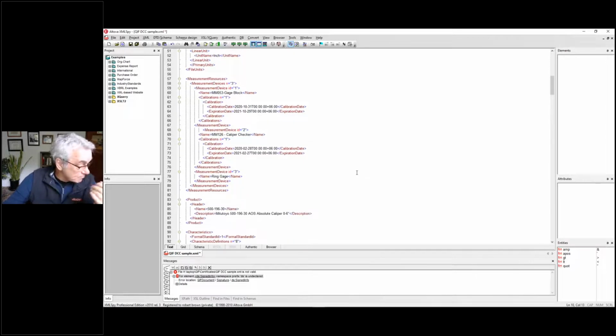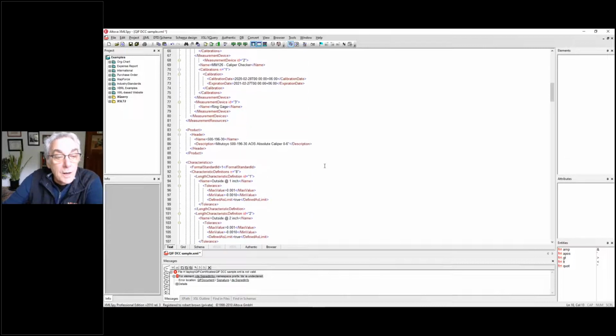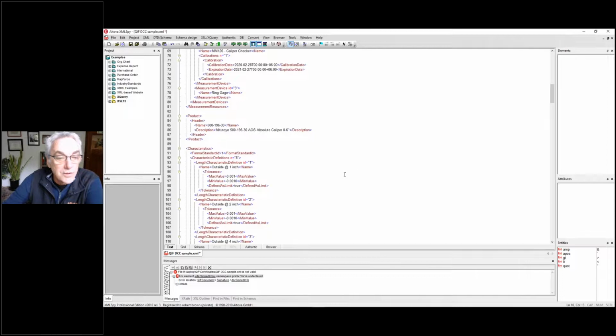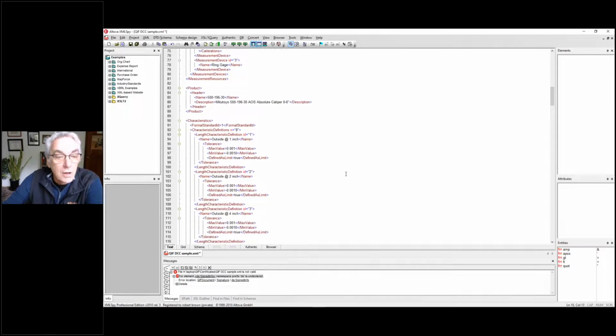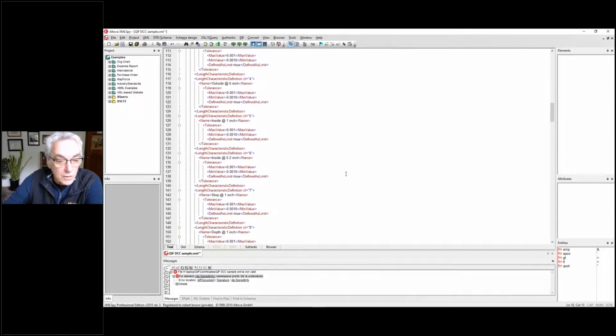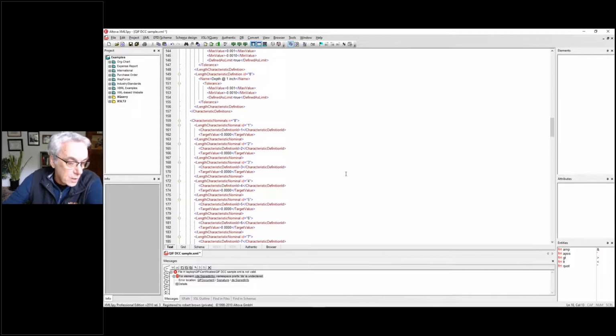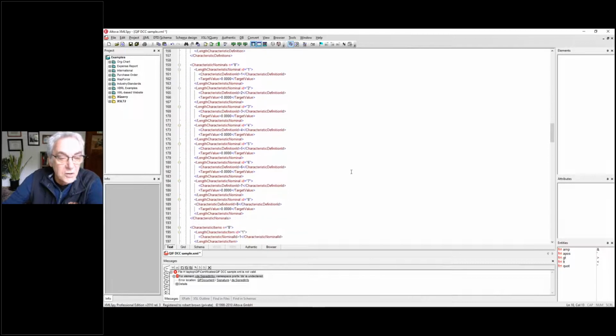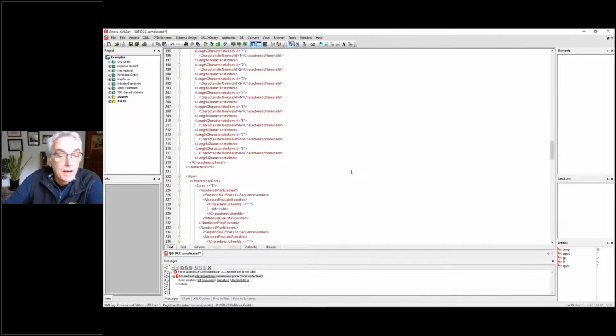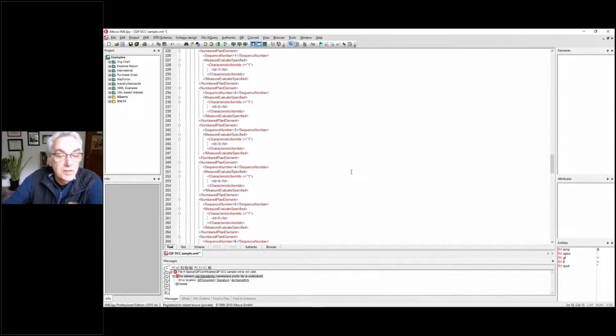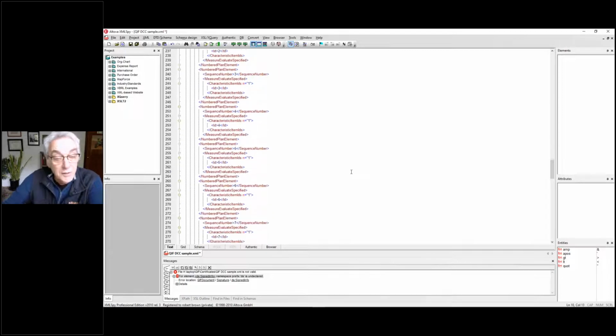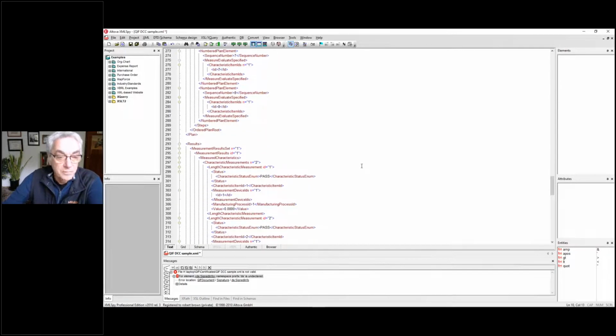The product, again, that caliper is a 500-196-30, which is a product code, and the description is again a 0 to 6 inch caliper. Characteristics, again, as we have the test points, we would understand it outside at 1 inch with its tolerance information. I'll just go down the line as we scroll to all of the different test points. We certainly have a nominal, and if we're doing an offset, so everything is 0. Ideally, we have the plan, which would be the sequence of the calibration procedure on the test points themselves, and then we have the results.